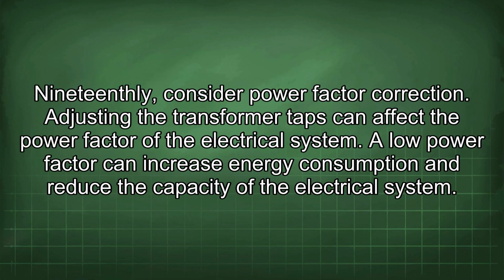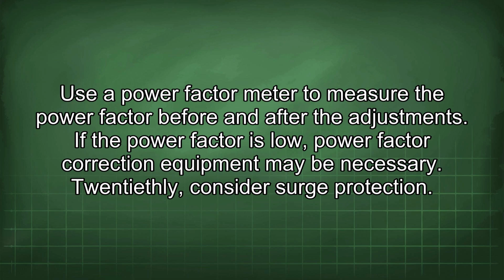19thly, consider power factor correction. Adjusting the transformer taps can affect the power factor of the electrical system. A low power factor can increase energy consumption and reduce the capacity of the electrical system. Use a power factor meter to measure the power factor before and after the adjustment. If the power factor is low, power factor correction equipment may be necessary.